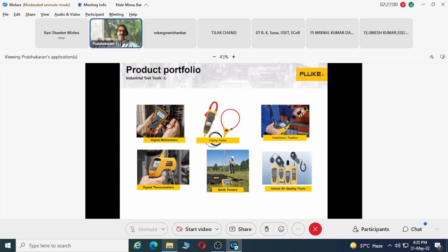In India, we have a customer regularly buying this who uses more than 50 units to my knowledge—it may be more—and he's a European elevator manufacturer. In elevators everything is metallic, so if there's a short circuit, the person on the elevator can get killed. That's why during installation and factory testing they use my product to verify whether their ELCB or tripping circuit is working. Many government customers also use it, but there's no standard as of now in India.